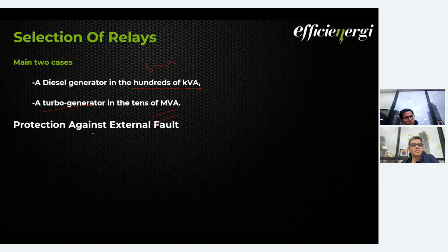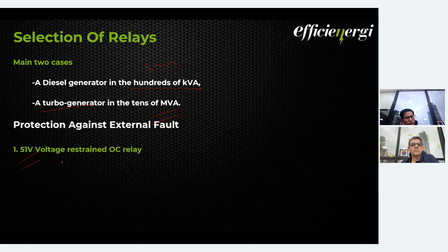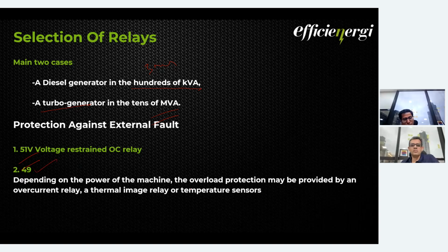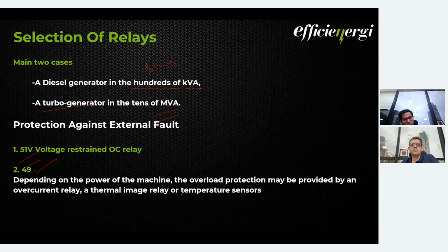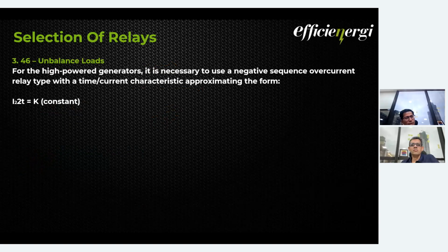So there the protections will be very stringent. In the protection against external fault, we are using 51 voltage restrained overcurrent relay. How this works, we will try to get the details of this in the next webinars. 49, as I told you, is for thermal overloads. 46 for unbalanced. 46 for unbalanced means this is a negative phase sequence relay, wherein I square T constant, if you have seen, is taken care of.